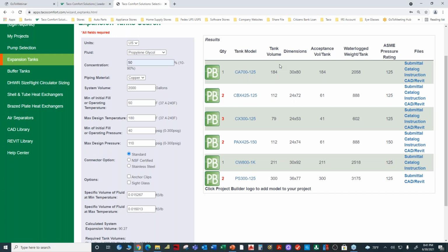Someone might be independent. Maybe they're off in a different part of the engineer's office and they're doing expansion tank sizing, not realizing that the design engineer on the other side of the office has decided that it's going to be propylene glycol. And the person doing the calculation thinks it's water. He makes the selection on water, but they actually use propylene glycol. Now the expansion tank is too small.